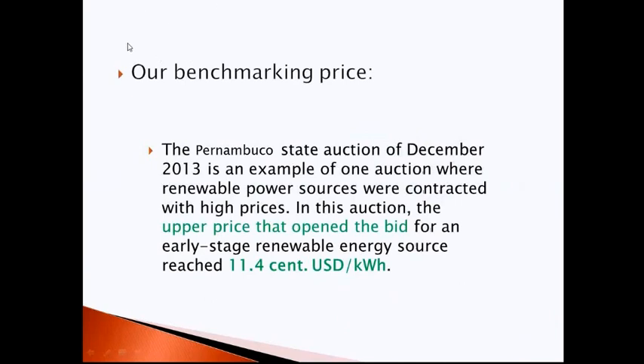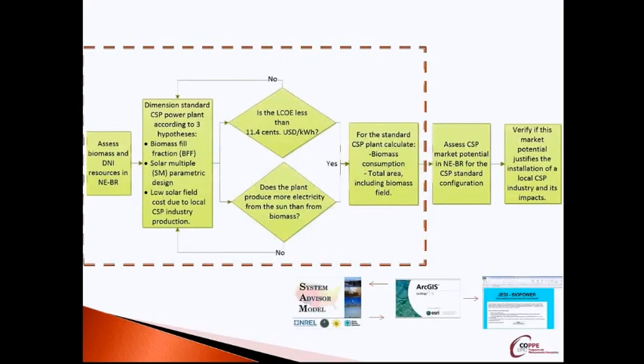We took as a benchmarking price of electricity the upper price that opened the bid in the Pernambuco State Auction, which happened in December 2013. The upper price in that auction was 11 cents per kilowatt-hour. Based on that, we simulated 30 megawatt CSP biomass hybridized power plants subject to two important restrictions: first, to produce electricity with a levelized cost of electricity less than 11 cents per kilowatt-hour; and second, that more than 51 percent of the annual electricity production should come from steam production from the solar field. This means we looked for a solar power plant hybridized with biomass, and not the opposite.